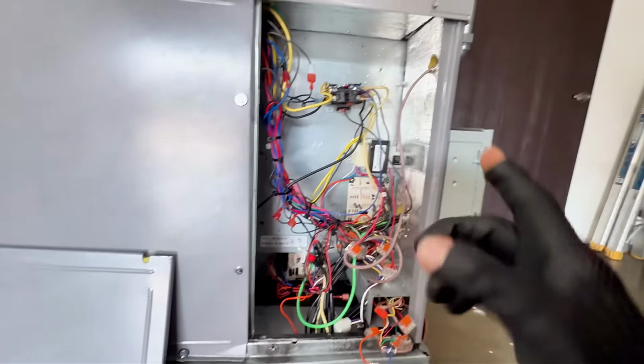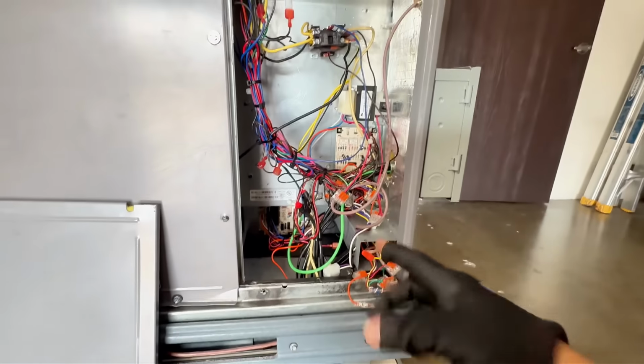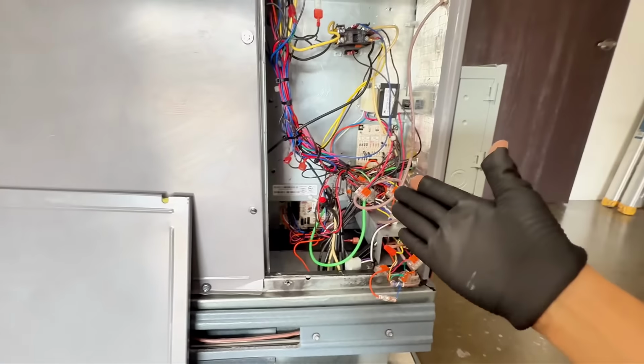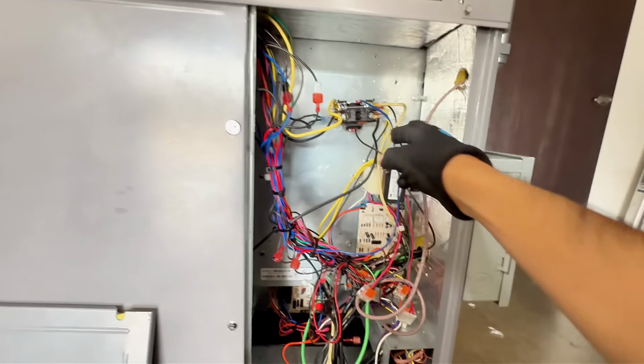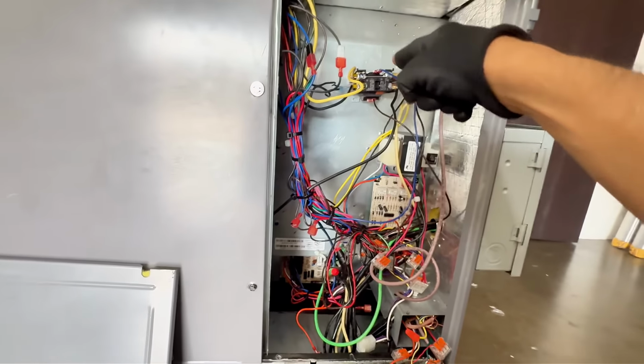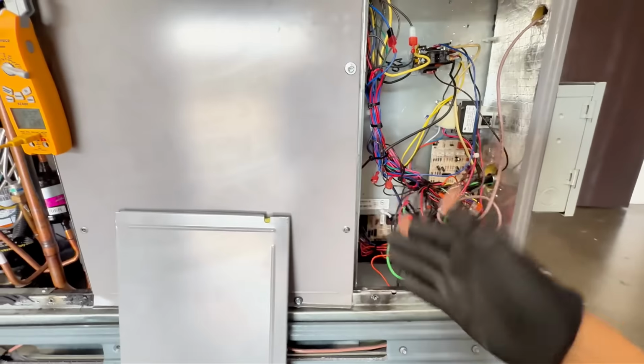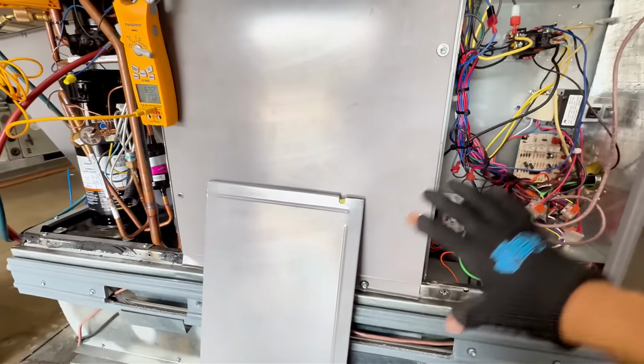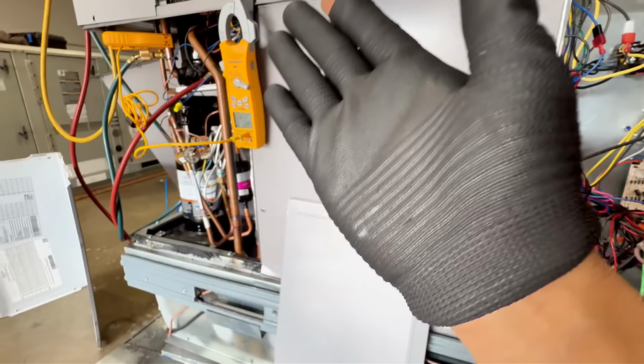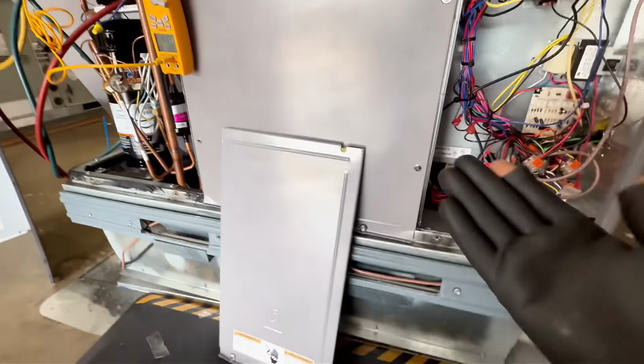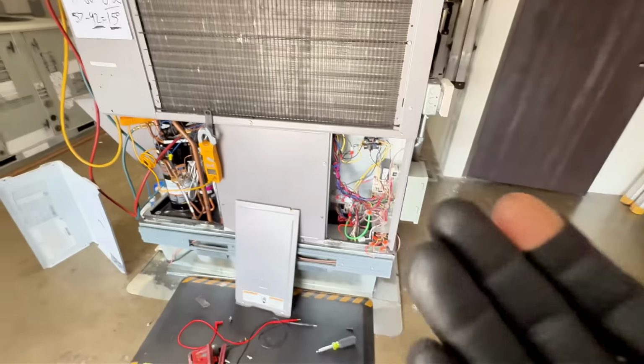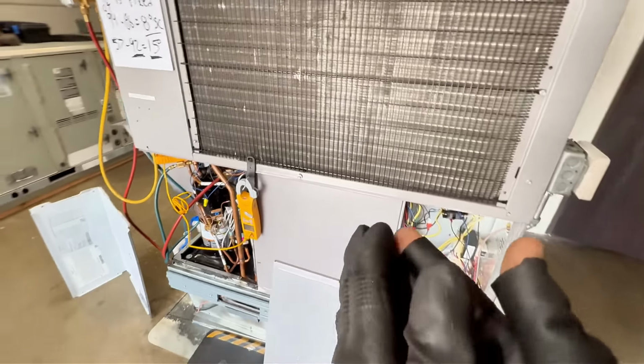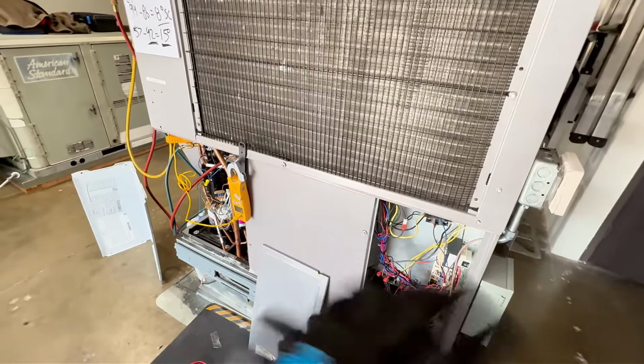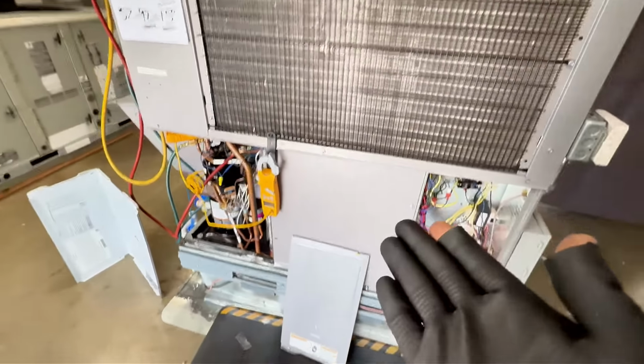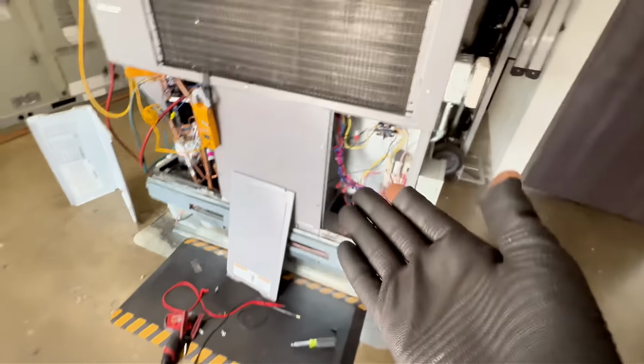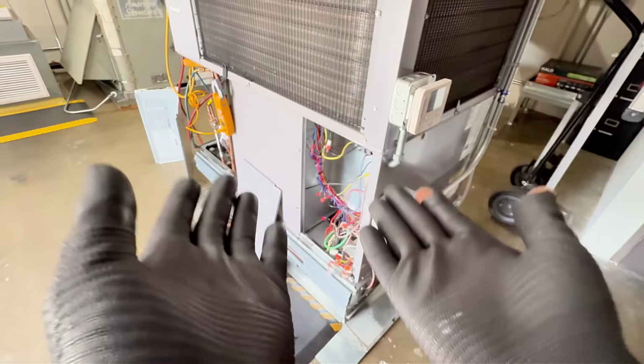The only thing is that the T, thermostat, well, there's more to it than just the thermostat. We've got to find out what's stopping 24 volts from going to the contactor coil, right? And I have videos on that that show the path that 24 volts takes and how to use your meter. So let me know if you want to start seeing more videos like these. I can have the students break down more stuff, give me more service calls, and you can see the approach, at least, that I take.